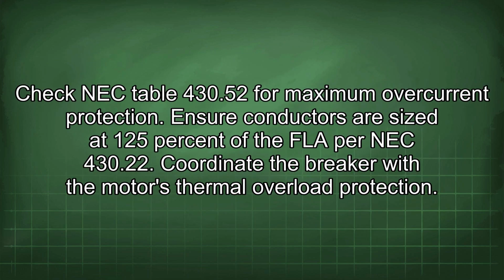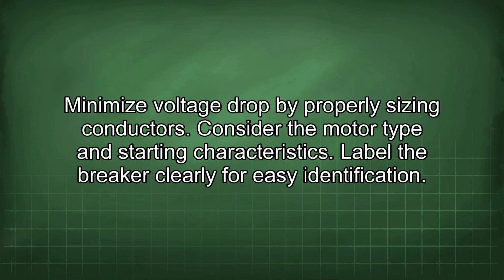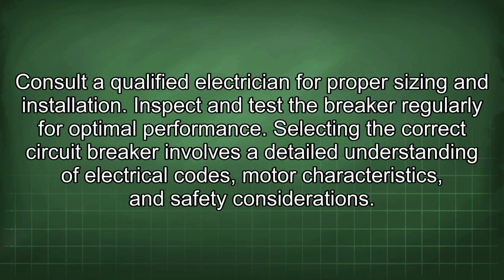Check NEC Table 430.52 for maximum overcurrent protection. Ensure conductors are sized at 125% of the FLA per NEC 430.22. Coordinate the breaker with the motor's thermal overload protection. Minimize voltage drop by properly sizing conductors. Consider the motor type and starting characteristics. Label the breaker clearly for easy identification. Consult a qualified electrician for proper sizing and installation. Inspect and test the breaker regularly for optimal performance.